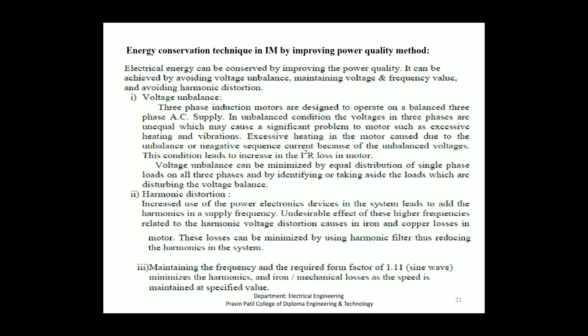Voltage unbalance. Three-phase induction motors are designed to operate on a balanced three-phase AC supply. In an unbalanced condition, the voltages in the three phases are unequal, which may cause significant problems to the motor, such as excessive heating and vibration. Excessive heating in the motor is caused by the unbalanced or negative sequence current because of the unbalanced voltages. These conditions lead to an increase in the I square R losses in the motor, that is, copper losses.